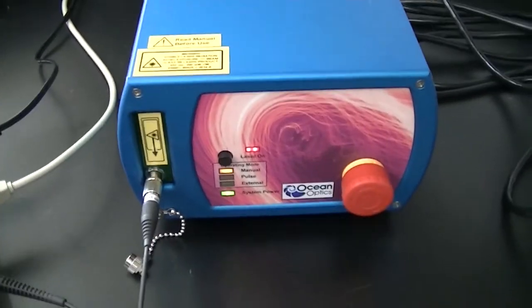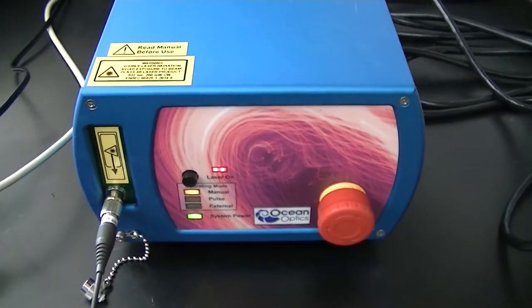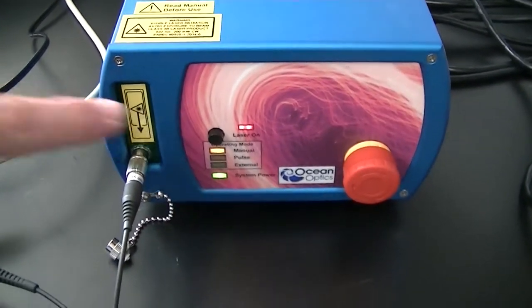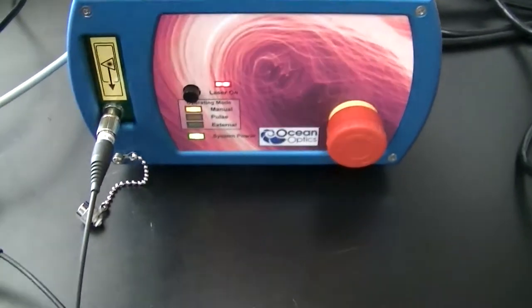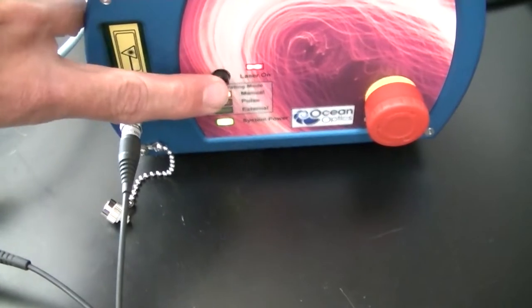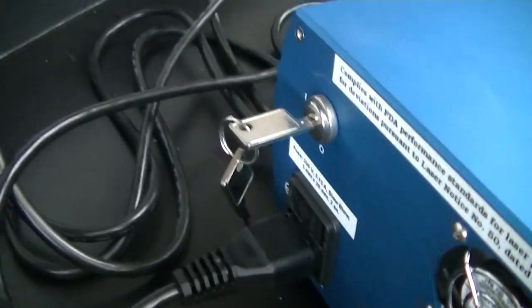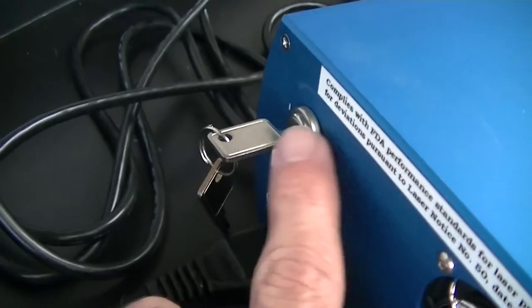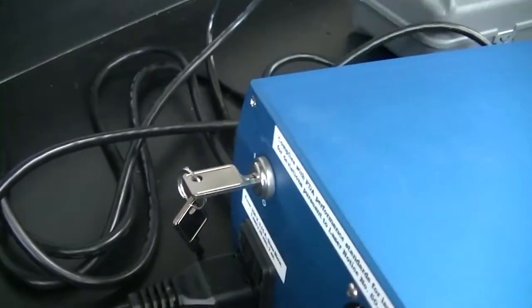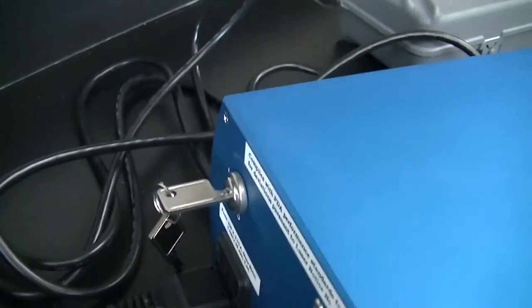This is the laser. It's a neodymium YAG diode laser. You can see here the indicator that the laser is on. This is a safety shutoff switch. This is the switch that turns the laser on. There's a safety interlock back here, which is the key. The key needs to be turned to on. And to turn the whole thing off, you turn off the switch, turn off the key, and then you unplug the laser from the wall.